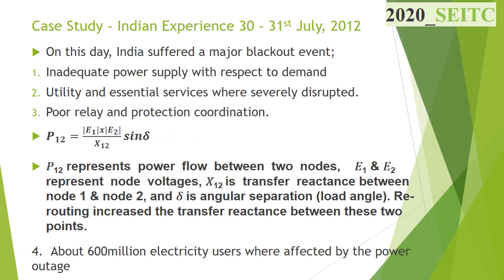Case study of an Indian experience of power outage that took place on 30th to 31st July 2012. On this day, India suffered a major blackout event. Investigation was carried out to determine the following: the precondition of the network prior to the outage, the initiating events, the cascade events if any, the final restoration of power supply to the affected area, and identify new challenges to a sustainable power system. At the end, the investigation revealed that there was inadequate power supply with respect to demand.